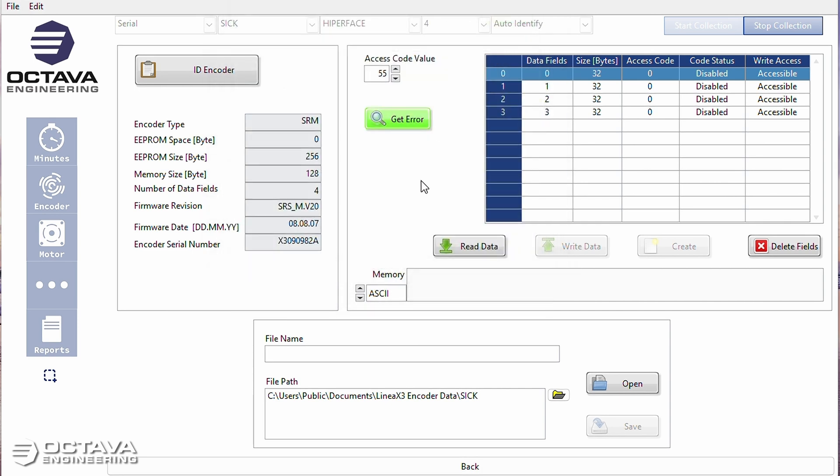So as bad as this encoder is, the encoder itself is only intermittently throwing faults out. So don't rely just on if the encoder is throwing a fault, if an encoder is good or not.